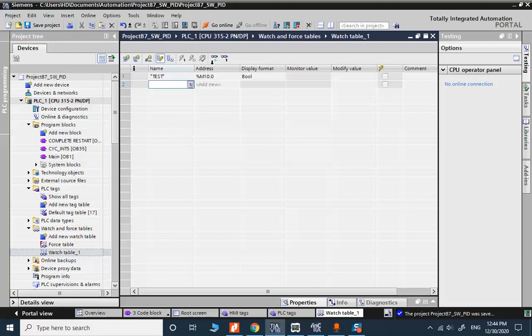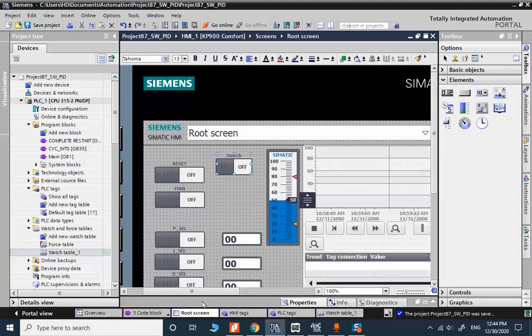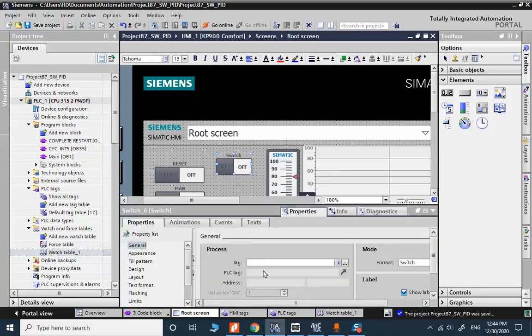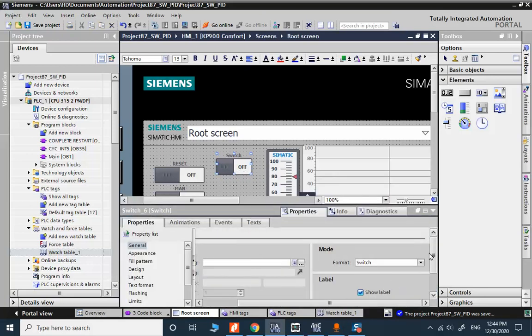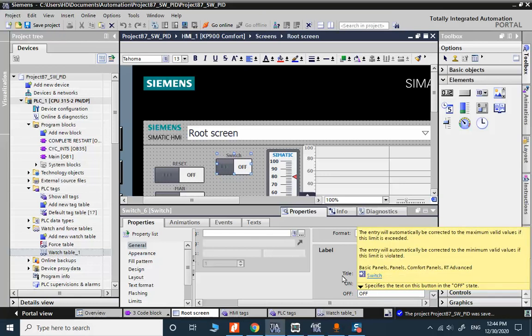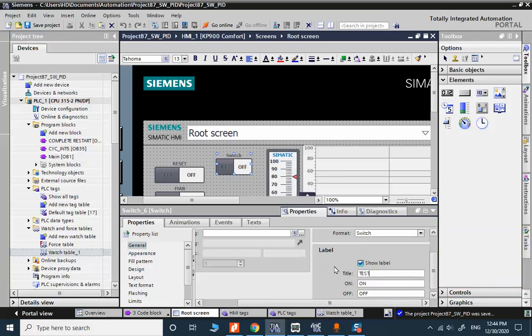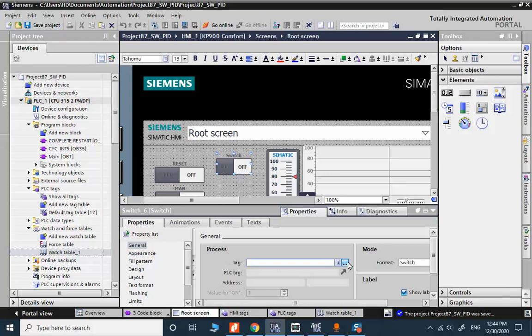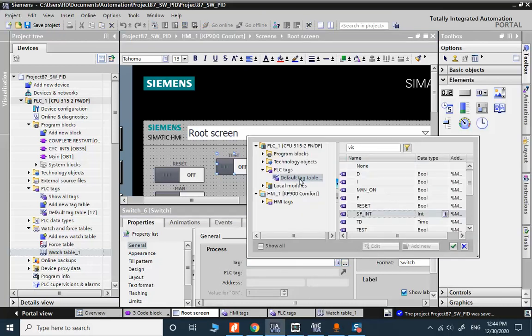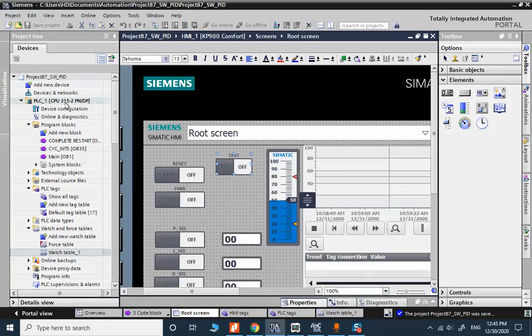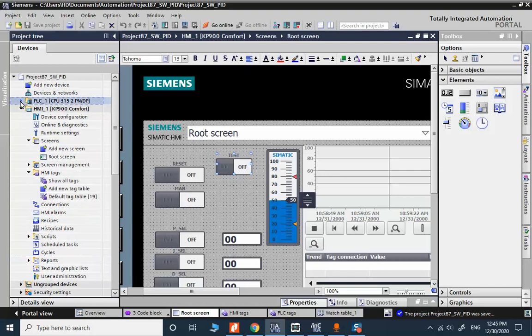The name is test and this variable is added. I need to link this variable to the switch. Right click, select Properties. In label you can change the title. You have the chance to rename the on and off status text. We can keep the default value here. It's also possible to give the tag address to that. Save and we go online for function testing this simple button here.